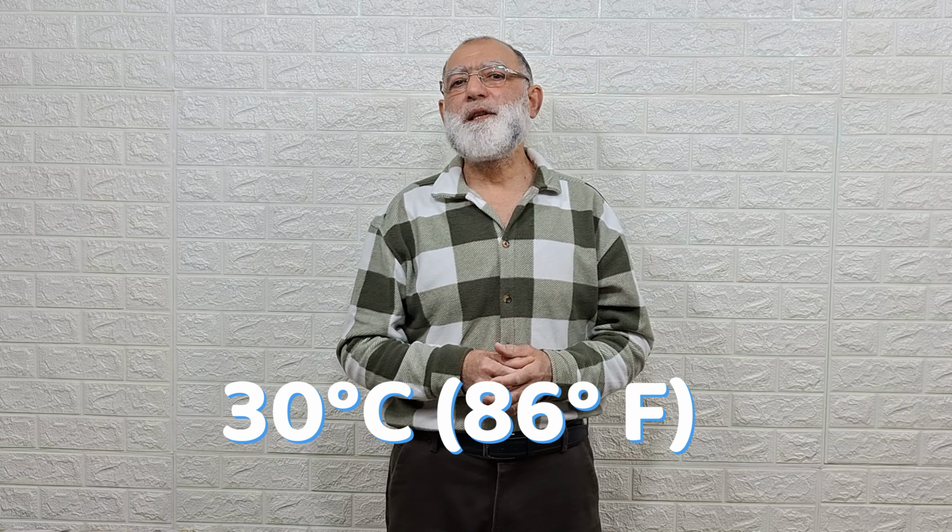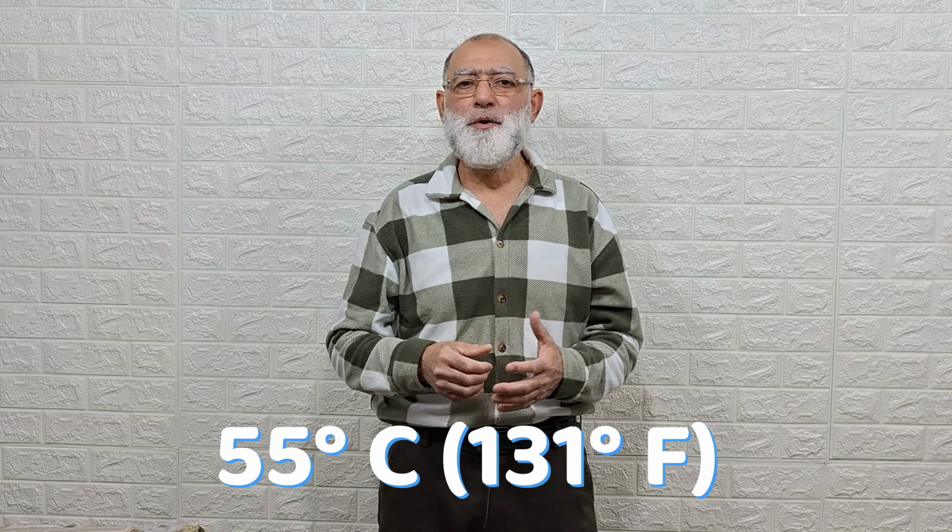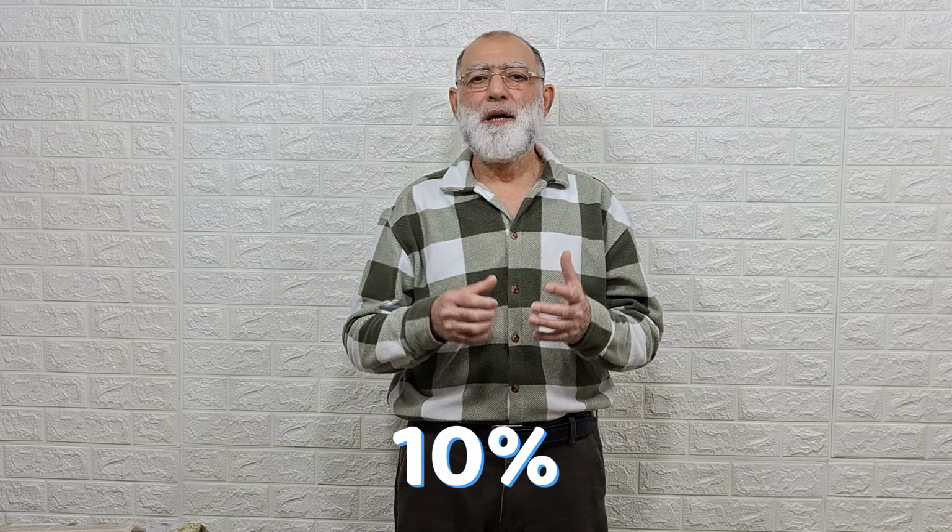For instance, if the air temperature is 30 degrees Celsius, the condensation temperature is typically 45 degrees Celsius. If the condensation temperature rises to 55 degrees Celsius due to a dirty outdoor unit, the net refrigeration effect will decrease by 10%.